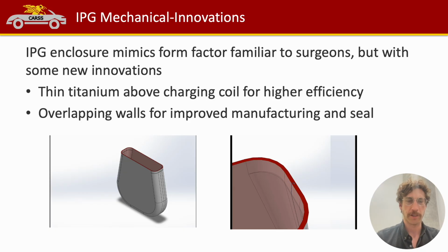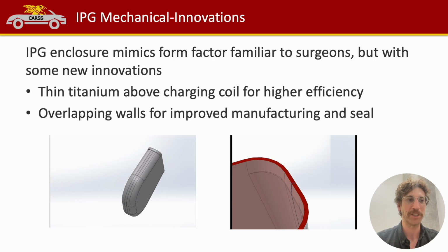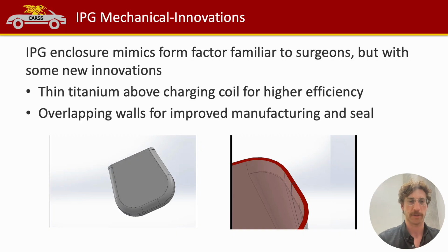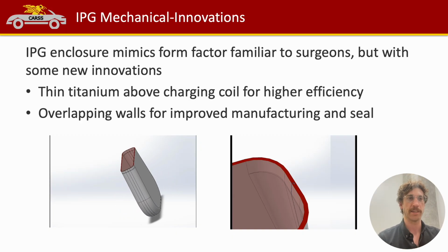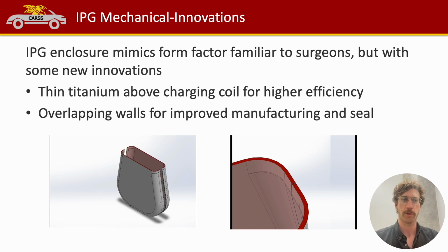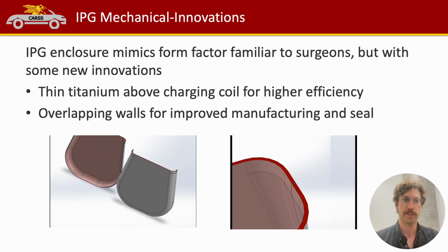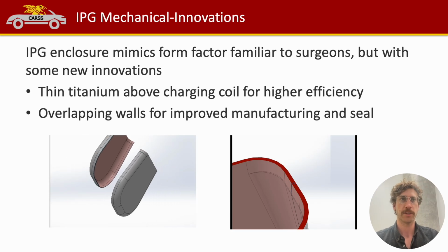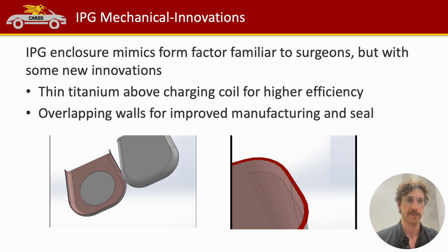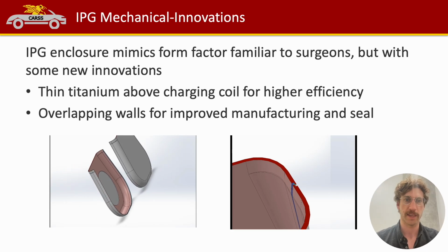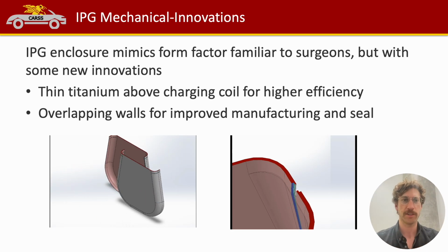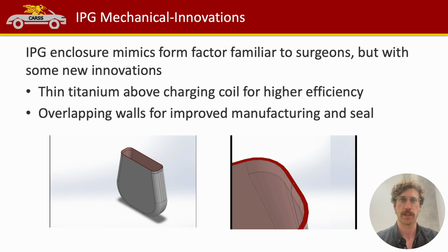So we're also doing some innovations in the actual enclosure design. One of the things MedAlly is doing is machining out the titanium just above the wireless coil. The idea being that this will attenuate the signal less and allow for more efficient charging with less heating. That's something we're excited to introduce and hopefully will improve the efficiency and improve the safety of these IPGs. Another innovation we're introducing is having overlapping edges on the walls of the IPG. This will help for improved manufacturing and improved quality control in creating that hermetic seal, that hermetic weld around the can.